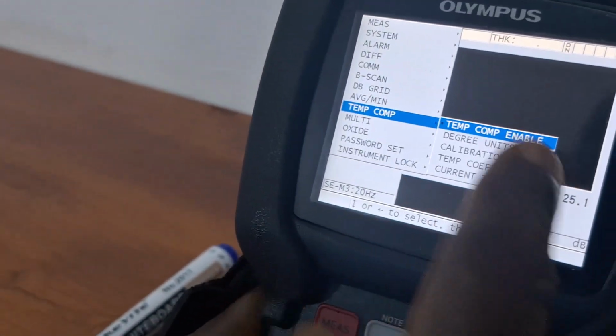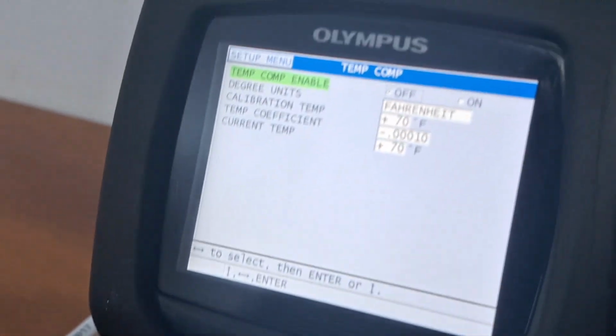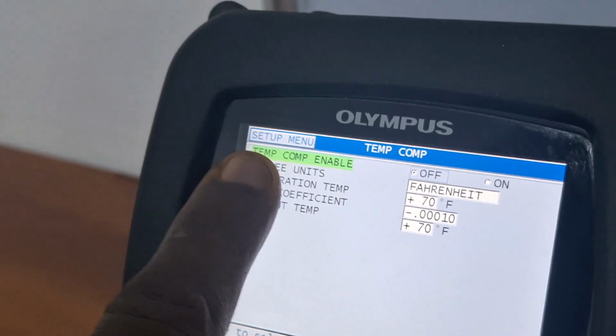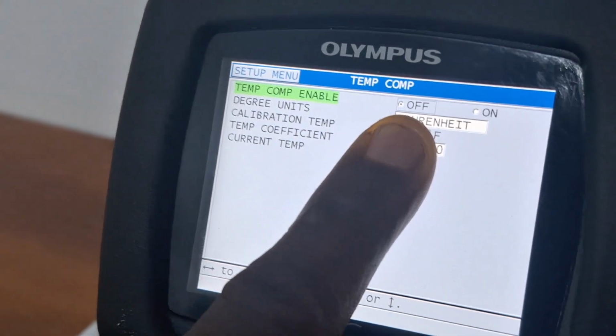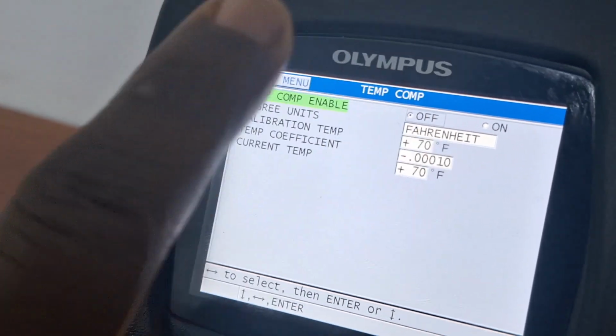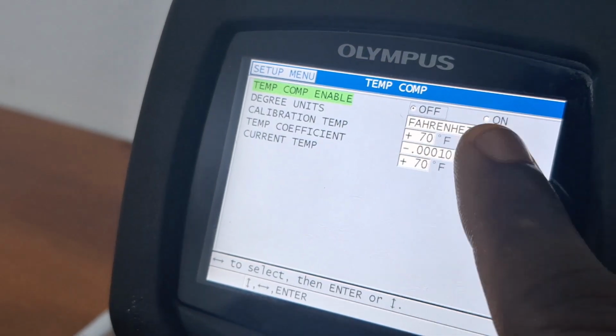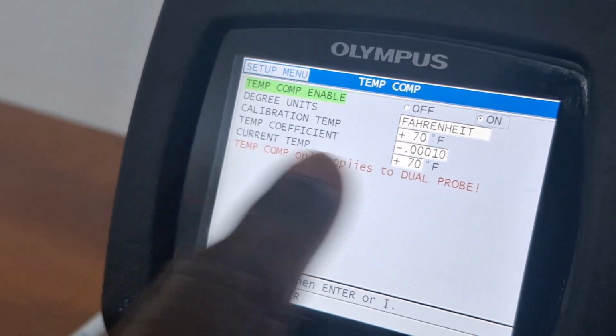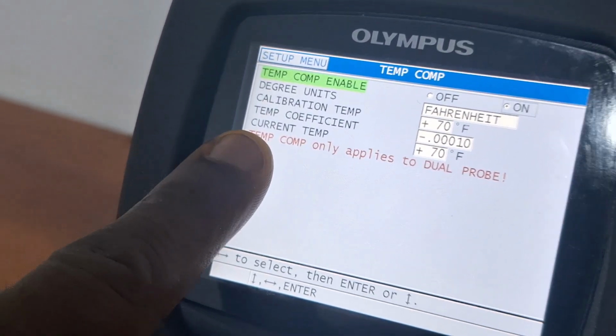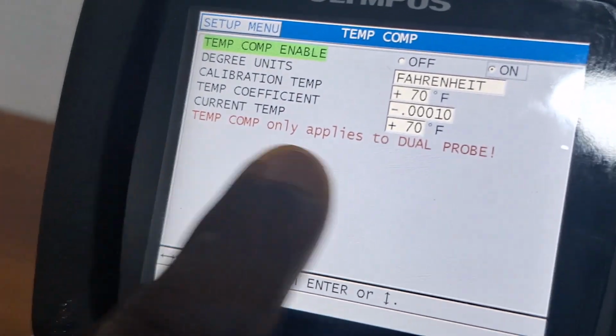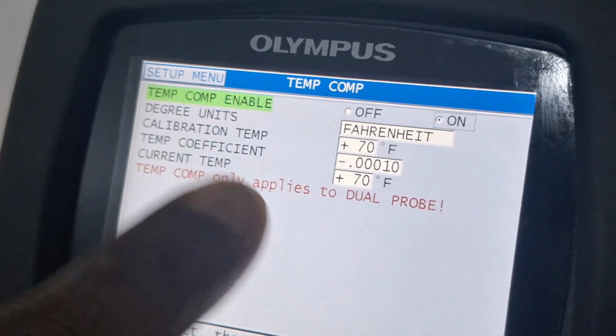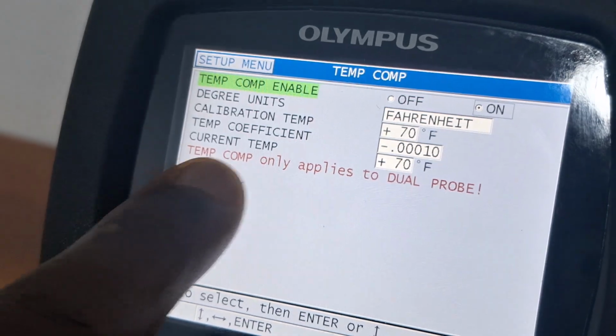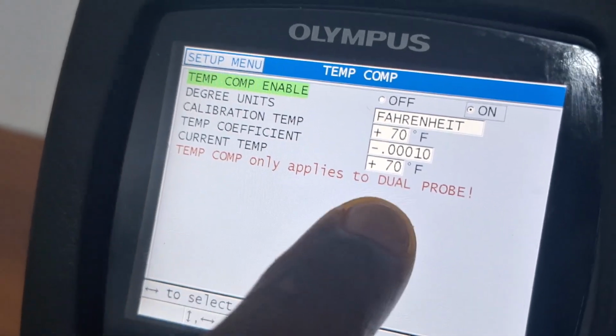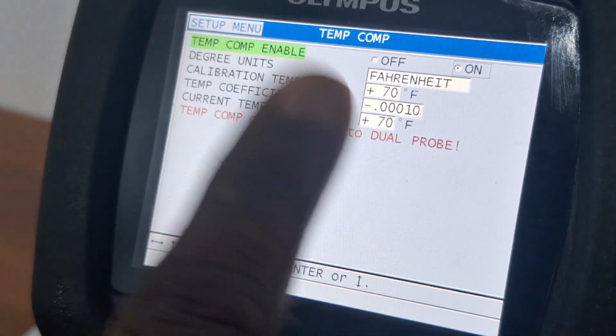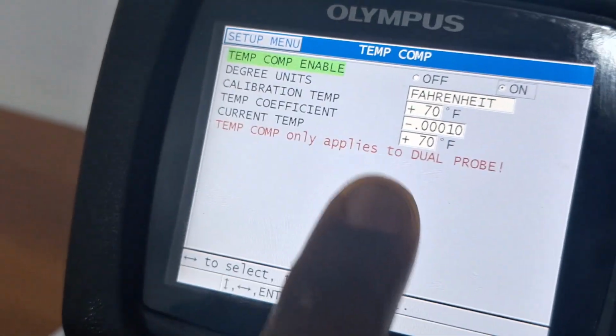So if I go to temperature compensation enable, it will give me a menu. From this menu now, you can see that temperature compensation is off. So if you want to do high temperature measurement, you need to go and turn it on. So now it's on. Now, there is a statement that is here. You really need to take this into consideration. So temperature compensation only applies to dual probe. So if you are using a single element probe, this will not support it.